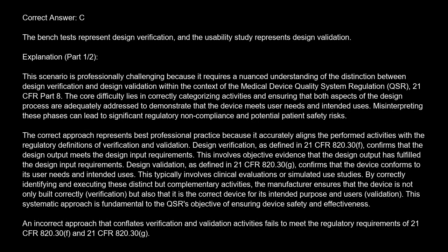The correct answer is C. The bench tests represent design verification, and the usability study represents design validation. Explanation: this scenario is professionally challenging because it requires a nuanced understanding of the distinction between design verification and design validation within the context of the Medical Device Quality System Regulation, QSR, 21 CFR Part 820. The core difficulty lies in correctly categorizing activities and ensuring that both aspects of the design process are adequately addressed to demonstrate that the device meets user needs and intended uses.